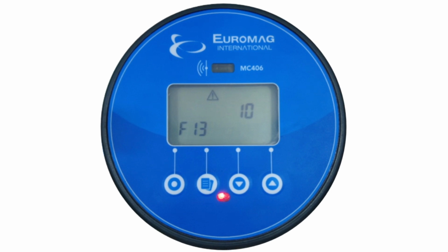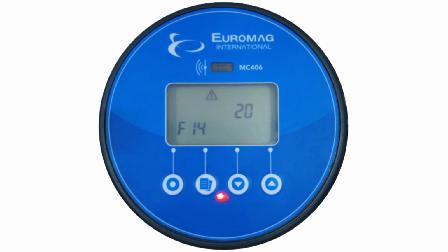Function number 13 is the bypass setting. With a value set to 10, measured samples that do not fluctuate by 10% will not be averaged in the damping equation. Function number 14 is peak cutoff filter. This value is expressed as a percentage. For example, a value of 20 represents 20% of the full scale setting, which is function 19. The peak cutoff filter will eliminate any samples that are 20% greater than the full scale setting.